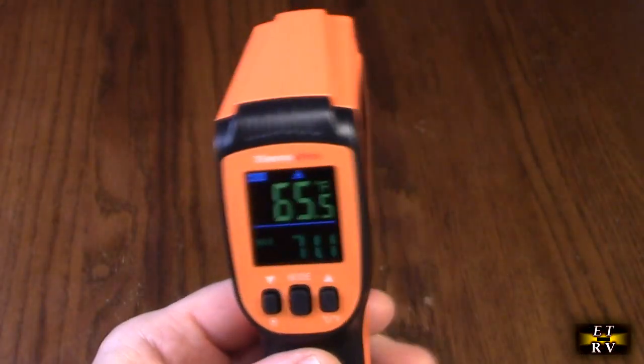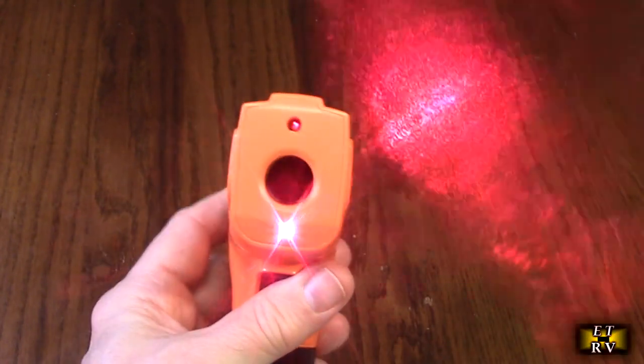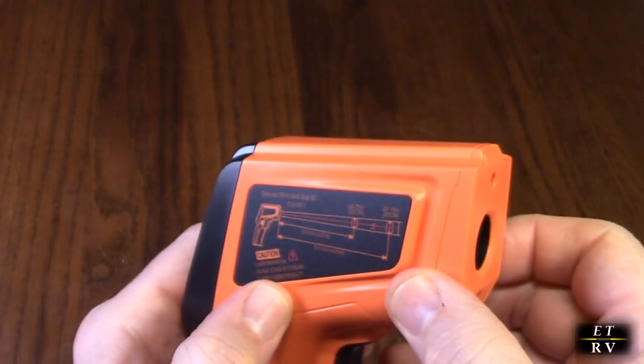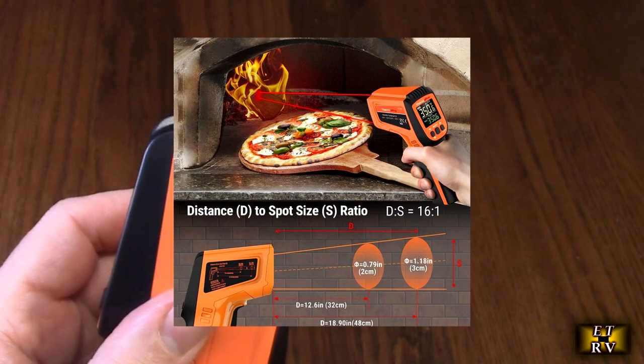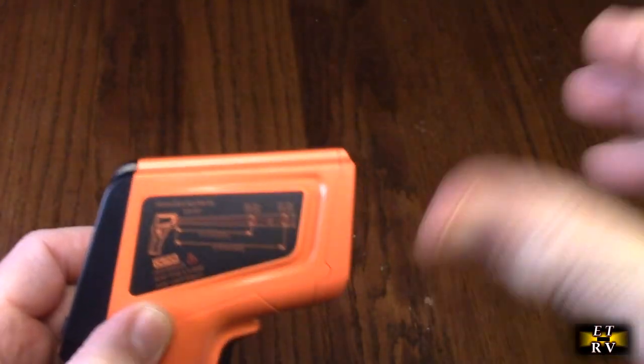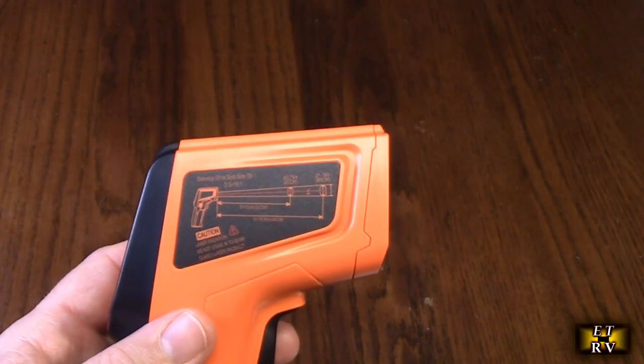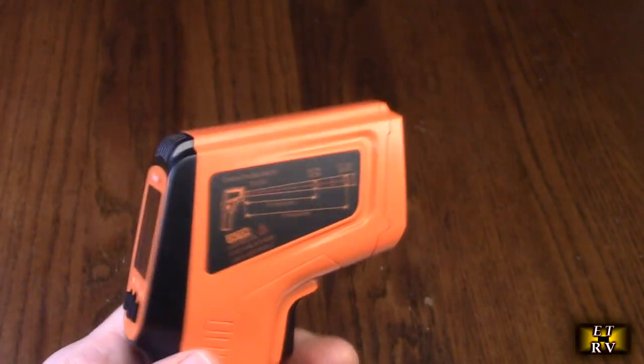Close the cover like that — really high-tech looking. When you push the button you get two laser outputs right there, and there's the thermal sensor. This has a ratio of 16 to 1. That dot ratio means that if you're 16 feet away, it's going to be a one-foot diameter area that it's measuring, which is really good because a lot of them have smaller ratios. This one is excellent for pinpoint accuracy using those two lasers.